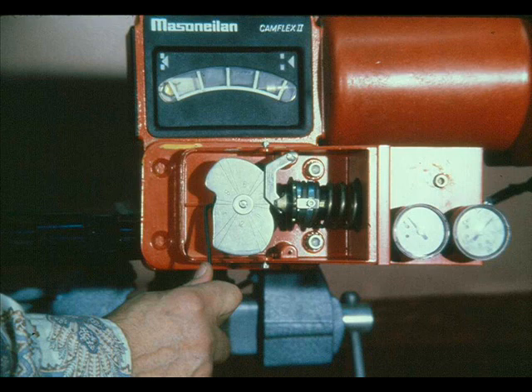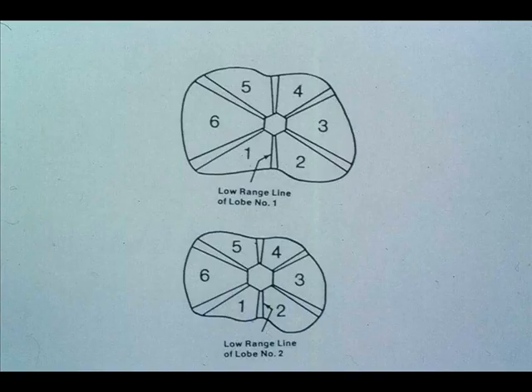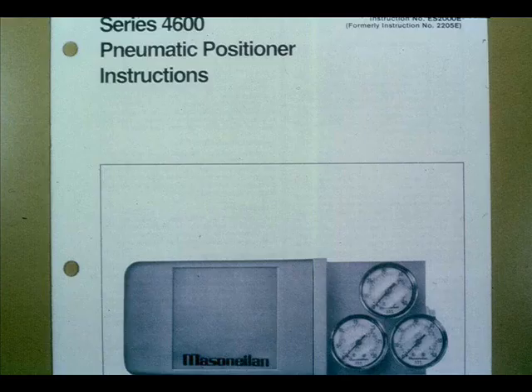The same 4600 positioner operates on both the CAMFLEX-2 and Sigma-F actuators, the only difference being two different CAMs — one for the CAMFLEX and one for the Sigma-F. Make sure you have the right CAM; the part number is stamped on each. Each CAM has two sides: one side has lobes 1–6 and the other side has lobes 7–12. The instruction manual gives examples showing the low-range line of the lobes, which is the line on the CAM that is aligned to the line on the positioner case for mounting.